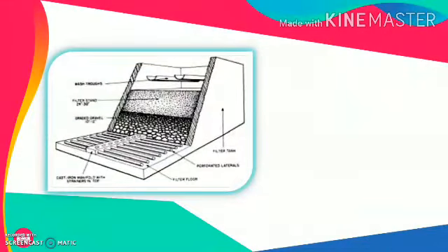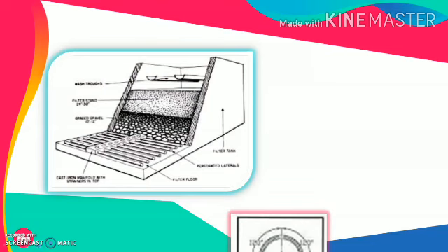This is a cross section of a rapid sand filter bed which shows the placing of such a collection system, in which a centrally placed larger diameter pipe of circular section has been provided, to which the laterals are connected. These laterals are perforated in nature. After the filtration process, the water gets collected into the perforated laterals and then is transferred to the central manifold.